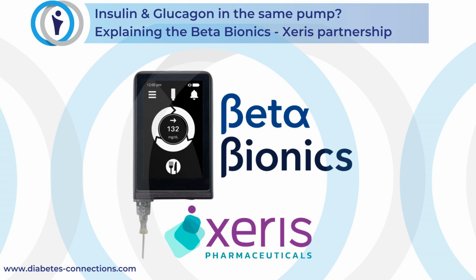Our current iLet device is an insulin-only device, but within that system, inside that box, is actually room for the other channel. So that's as big as the system will be. One of the criticisms or concerns we've had in the past is, wow, isn't this thing going to be really, really big? The answer is no. It fits within our current pump today. So that's been solved. The algorithm is there. We've done roughly 20 clinical trials on this over the years. It works. The remaining domino that had to fall, as Paul alluded to earlier, is the existence of a drug that had the formulation, the concentration, the stability, and the compatibility to be able to work in our product. And we believe we have that now.